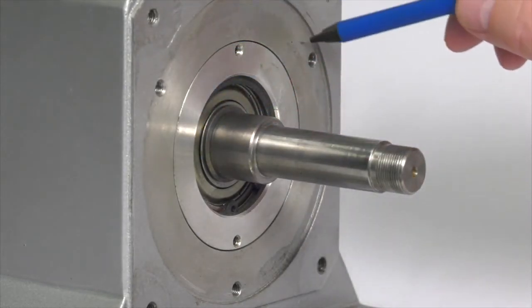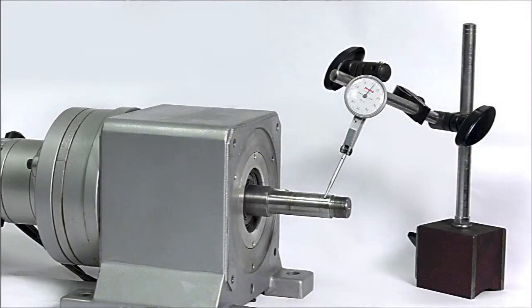Although some Ogura brakes allow a slightly larger perpendicularity, most Ogura brakes require that the tolerances be held to two-thousandths to four-thousandths of total indicator runout.